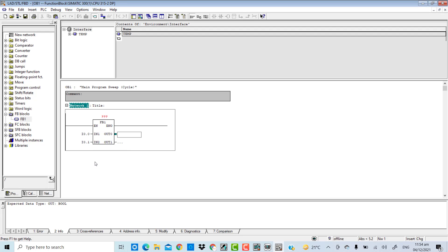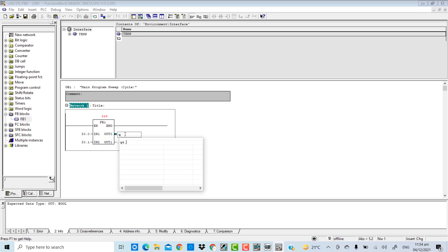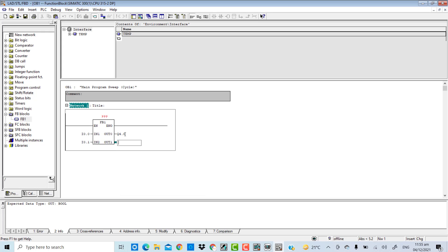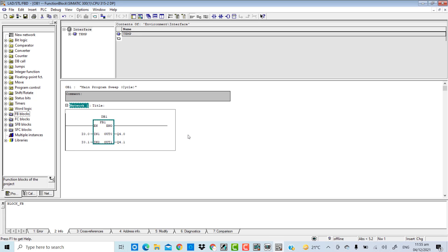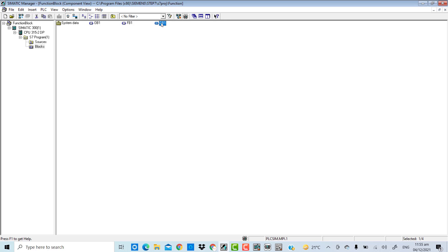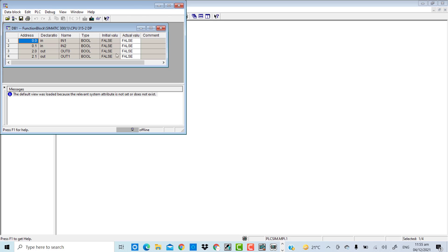In OB1, I will be passing digital input signals I0.0 and I0.1 to FB1, and storing the results into outputs Q4.0 and Q4.1. Since this is a function block, you may be aware that a function block has an associated data block — it has instance memory in which all the parameters of the function block are stored. I will name it DB1. A message pops up telling me the instance data block DB1 does not exist — do I want to generate it? Yes. It will be automatically generated, and if you click on DB1 in Simatic Manager, all the parameters will be updated automatically.